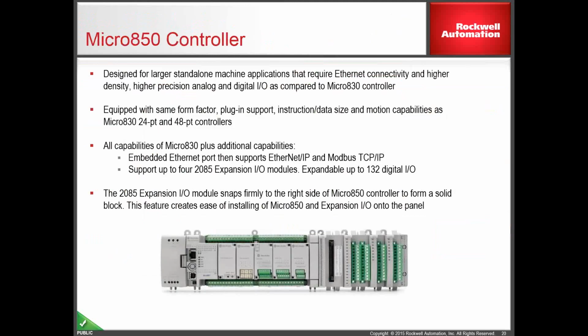This gives you a complete overview of the 850 controller. So it has got all the functionality of Micro 830 with the additional capability of an Ethernet port. As I said, it supports EtherNet/IP and Modbus TCP/IP, and supports up to 4 expansion I/O modules, which is expandable up to 132 digital I/O locally, and it can go remote as well.